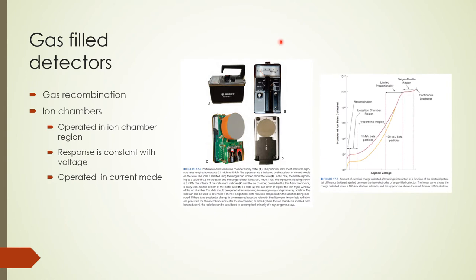A gas-filled detector can be operated in various response regions depending on the applied voltage between the electrodes. The voltage-response curve shown on this slide illustrates the different regions of operation. We shall start with the recombination and ion chamber regions. When ion pairs are produced in a gas, if the applied voltage is not high enough, the ion pairs recombine — this region is called the recombination region. When the voltage is increased until the ions are no longer recombining, we enter a plateau region called the ion chamber region. In this region, the response does not change significantly with voltage. Ion chambers are operated in the ion chamber region in current mode and can be used in high radioactivity environments.